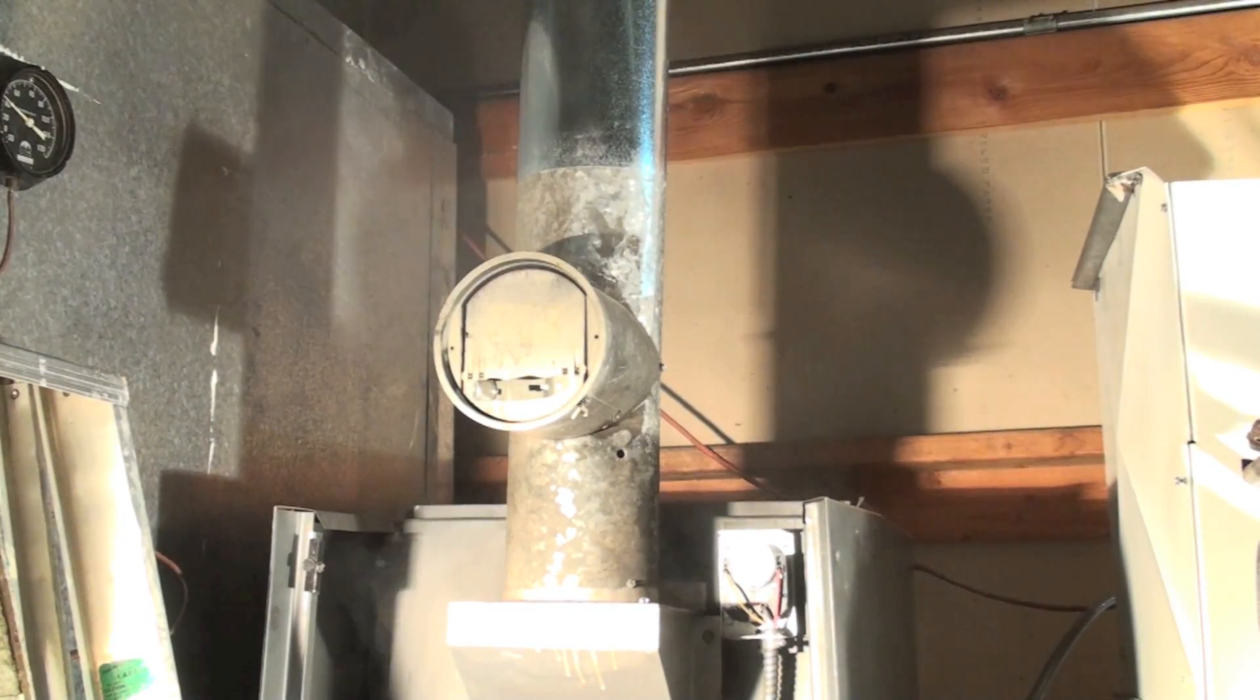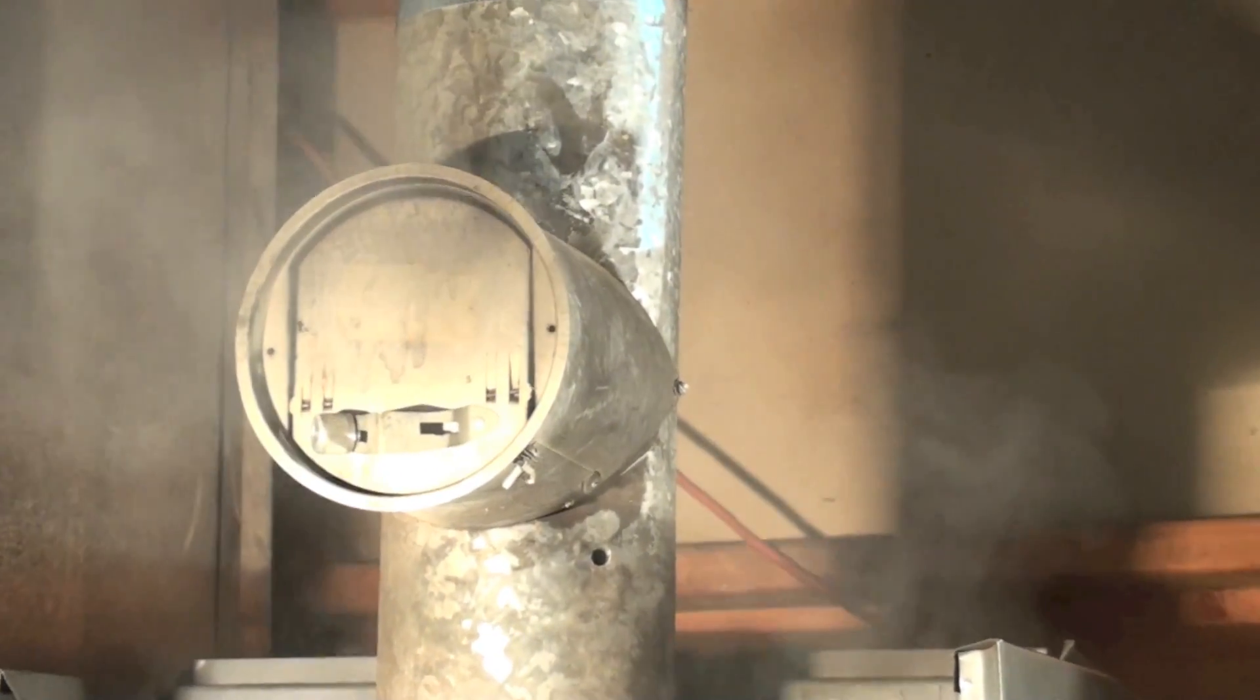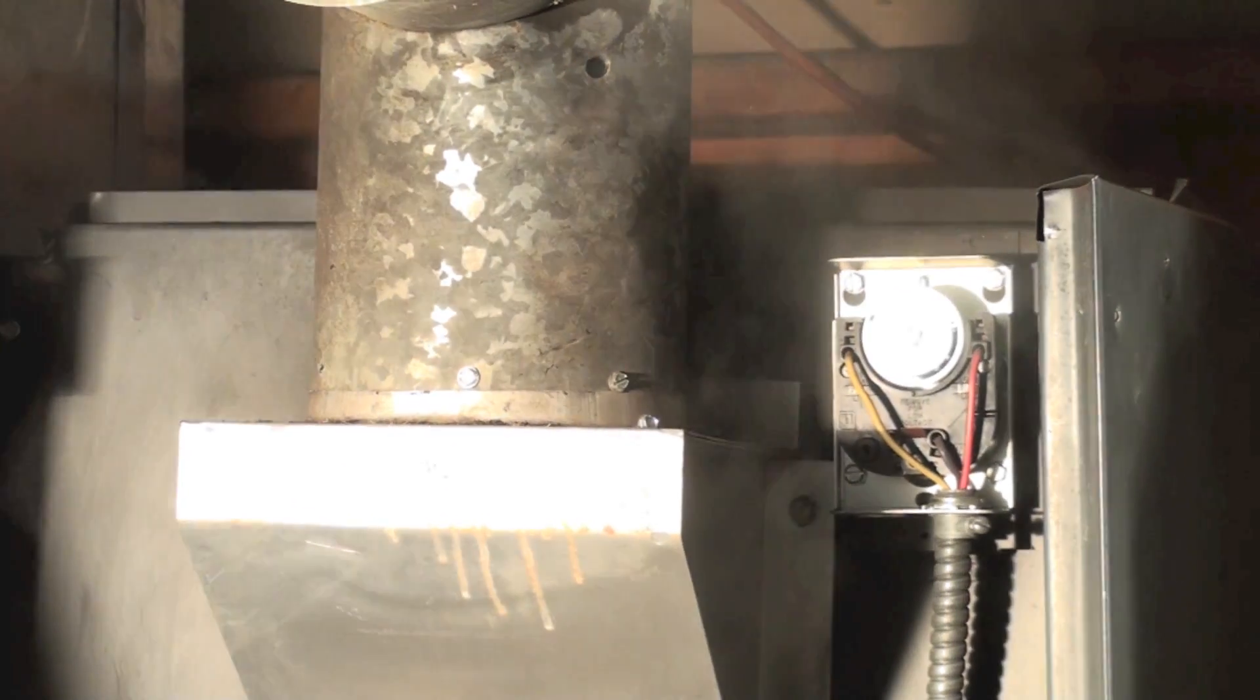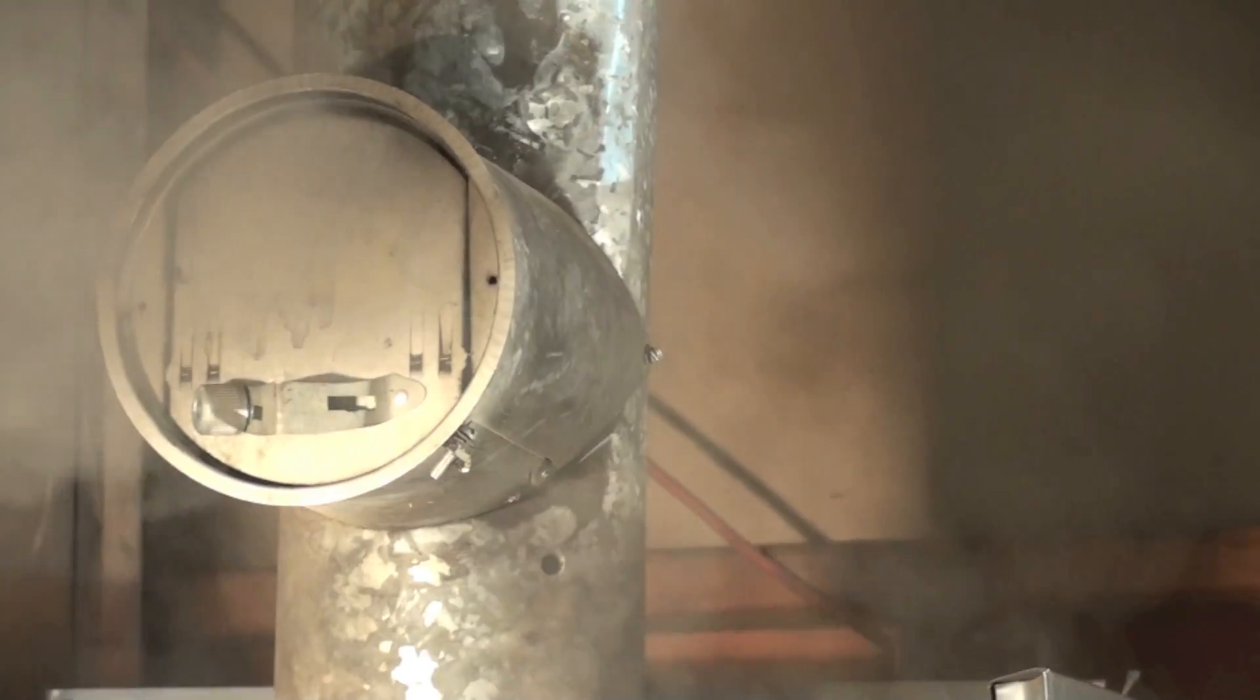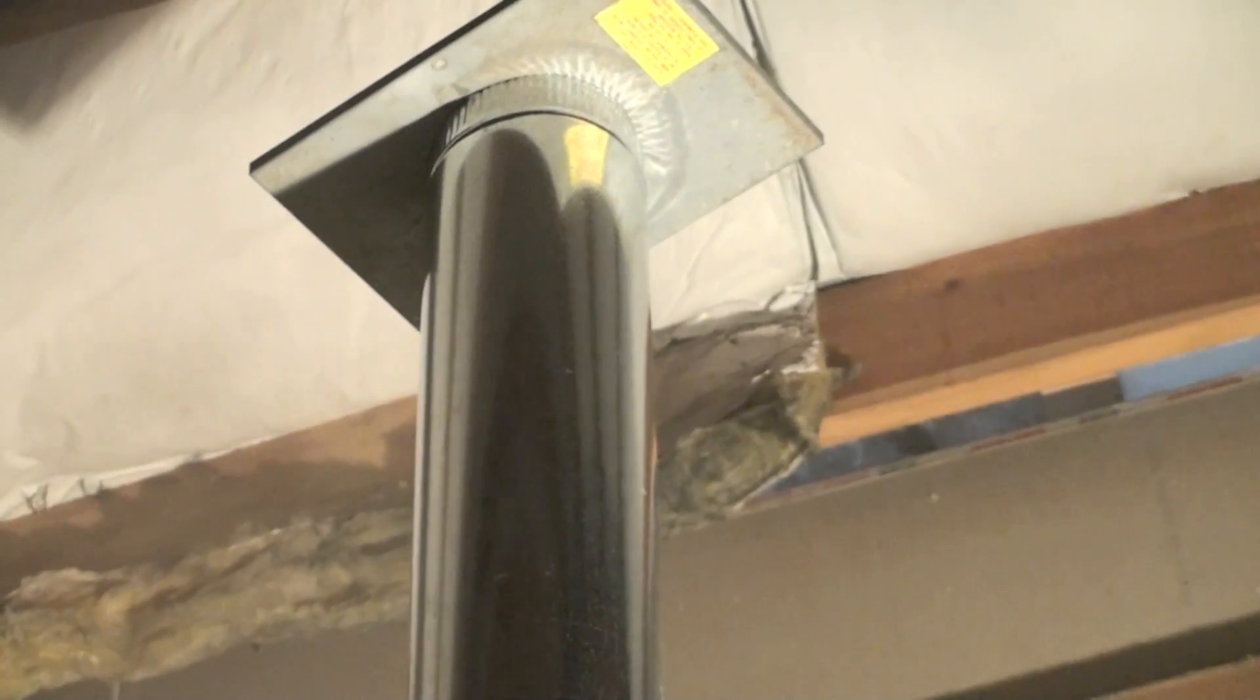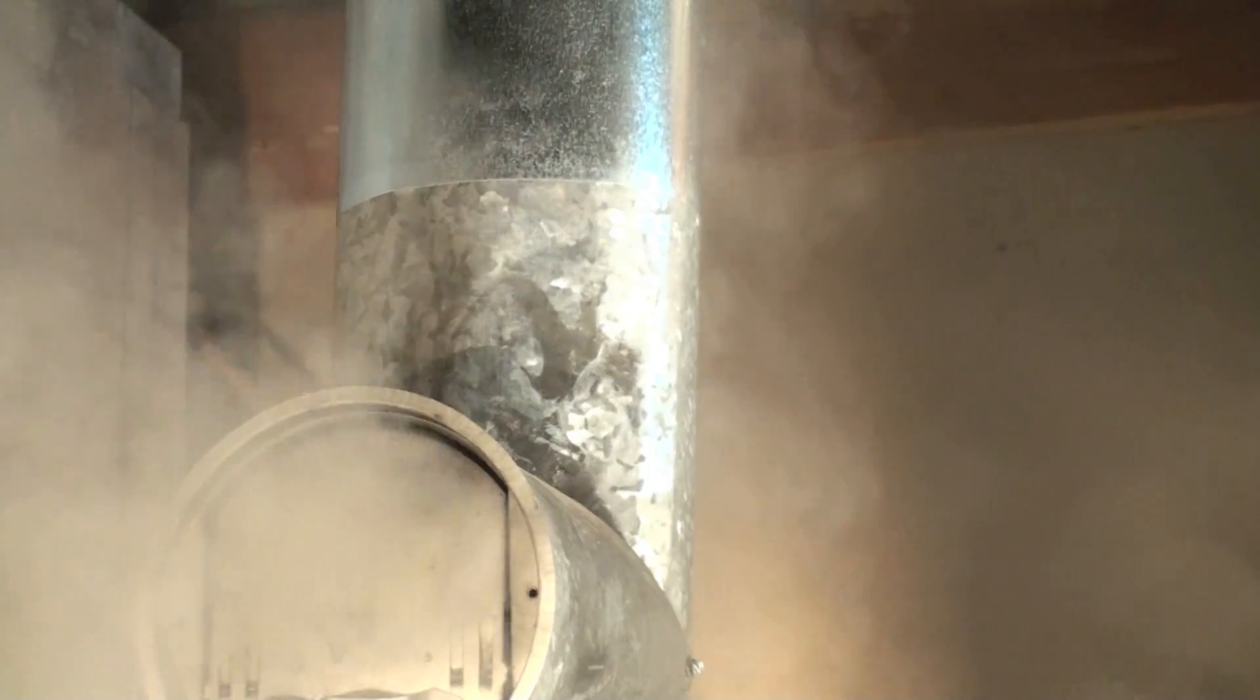I'm plugged, and you should be able to see there's smoke coming out of every place. It's coming out from down below, from the combustion chamber, everywhere but up there. You see it's all blocked off, so that little hole doesn't mean anything if there's a positive pressure in there.